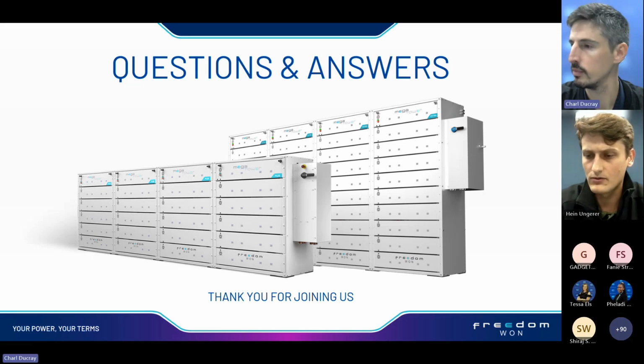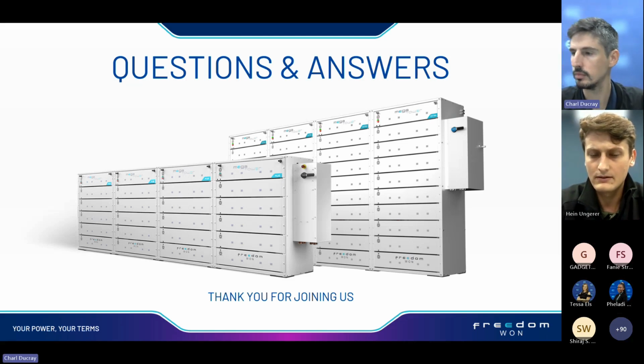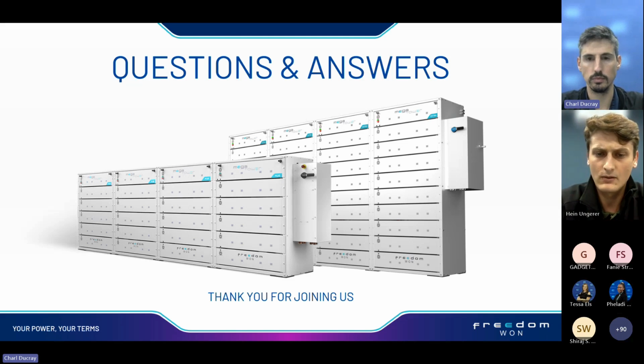I see Roy has a question on on-site assembly, about the size and weight of each battery module. Each module weighs around 250 kilograms. For the megaTower Plus, we can build it on site with a hydraulic trolley. For the megaTower Extra, where there's no access for a forklift, we designed a lifting system that bolts onto the rack, and then we can lift the modules up to the topmost slot to push the modules in.